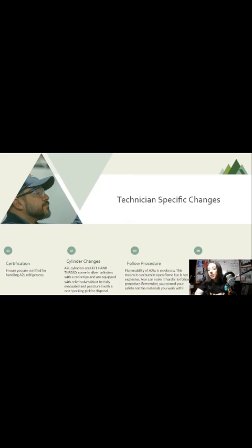Transport changes. A2L cylinders must be transported so that the vapor phase is in communication with the safety relief valve at all times. This means upright. DOT will offer certain waivers for situations where you cannot carry it in an upright position. But for regular service technicians who drive around in a van, your sideways refrigerant holders will no longer be a thing. You will have to turn them upright. Again, if we have a high amount of pressure in an A2L, we want to make sure the vapor is releasing through the pressure relief valve, and that it's not building pressure within the cylinder and eventually blowing up or catching fire.